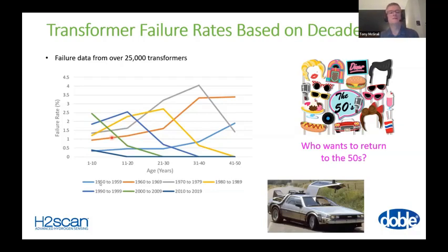Then you get to the 1970s, the gray line. And again, it's that rise in the first 10 years, next 10 years, and so on. And so what we're seeing is that the unreliability seems to be coming in earlier. And this has got nothing to do with individual manufacturers. It's got nothing to do with individual designs. This was just a general population. And a general thing to note is that those transformers built in the 50s seem to last a lot longer before they had some significant unreliability. Again, you move into the 80s, you move into the 90s, and that initial peak is getting sooner and sooner.